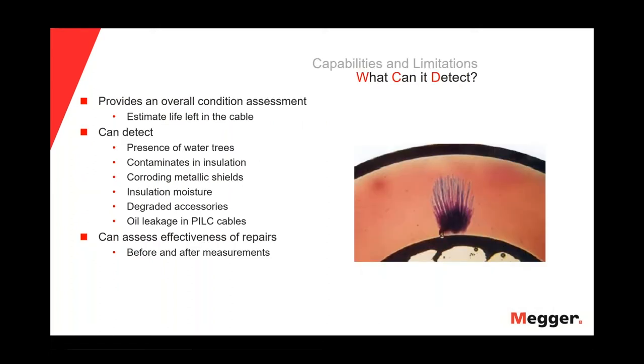So what are the capabilities and limitations of the tan delta test? What can it detect? Well, for sure, it provides an overall condition assessment. We can estimate the life left in the cable, and we can detect the presence of water trees. We can detect contaminants in the insulation, corroding metallic shields, insulation moisture, degraded accessories, and oil leakage in the case of oil-filled cables. And of course, we can assess the effectiveness of repairs by measuring before and after.